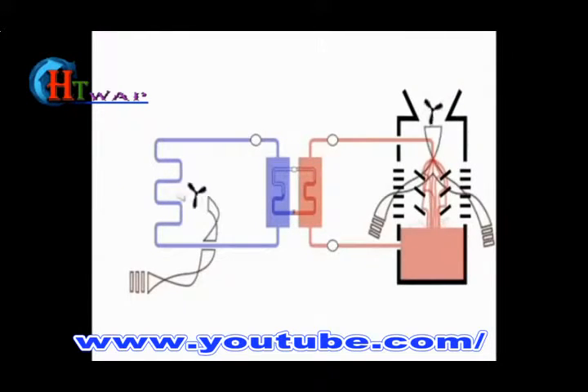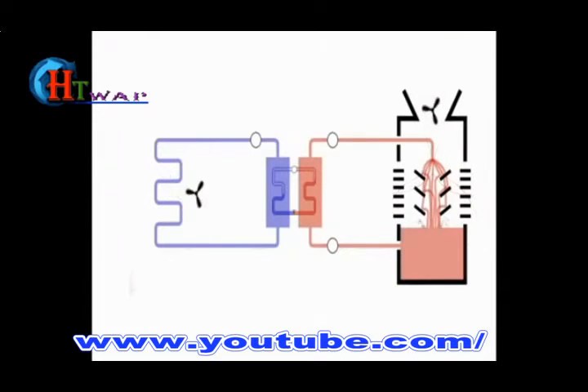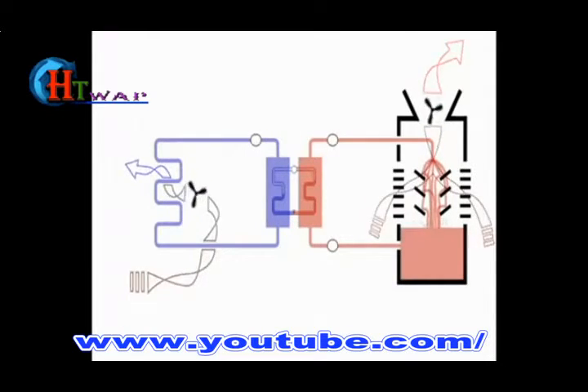This distribution network using water is complicated, but not exceptionally complex. Let's review. Water is cooled by the evaporator and distributed to the air handling units to cool room air. A separate loop of water cools the condenser and carries its heat to the outside air via a cooling tower. You've seen cooling towers on roofs and adjacent to buildings, or as part of central chiller plants. The machine that does the compression refrigeration loop in this layout is termed a chiller. As we've seen, the recirculated air is cooled by the chilled water.